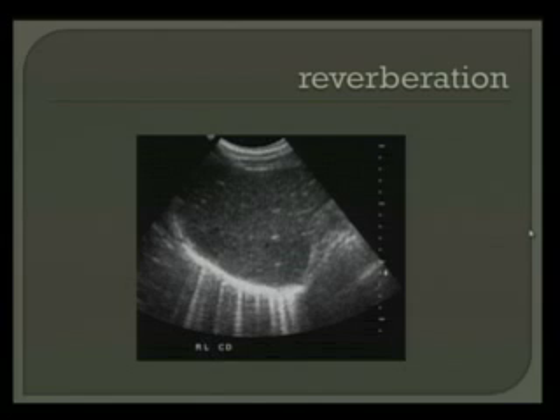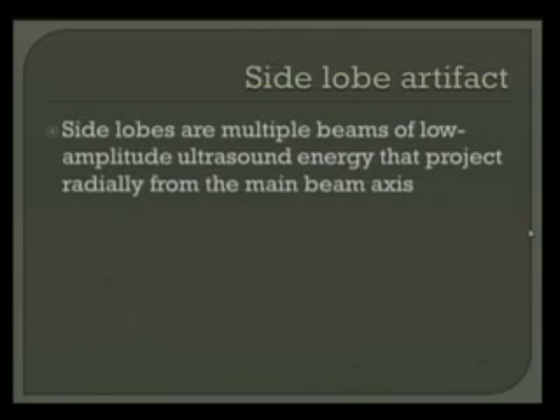In real time, you will see that these are moving, right? Of course, for diagnosis of pneumothorax, you have all your A lines and other lines, but sometimes diagnosis is very possible when you can see the reverberation in real time. Sidelobe artifacts are multiple beams of low amplitude ultrasound energy that project radially from the beam axis. So something should come down, but it diverges, and it erroneously gives us a larger size of that object or that mass than it normally should have because of the sidelobe artifact.